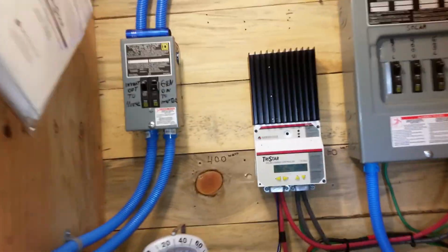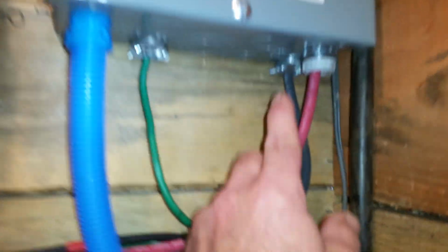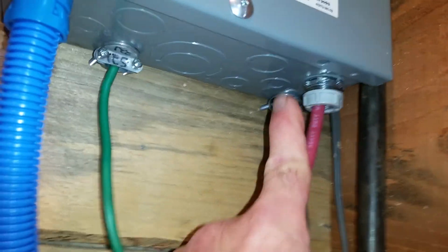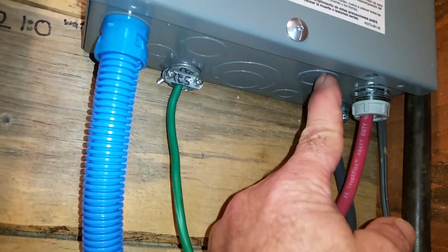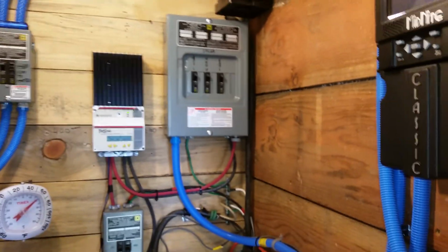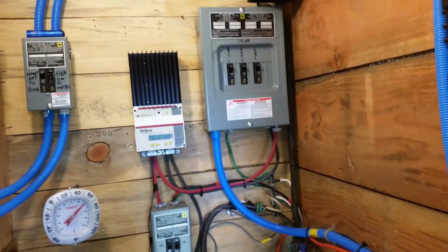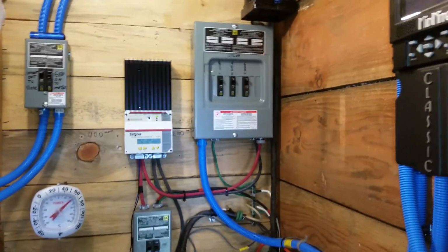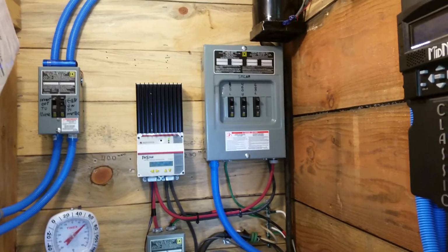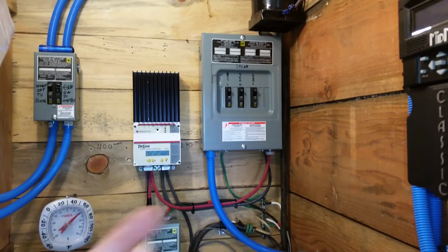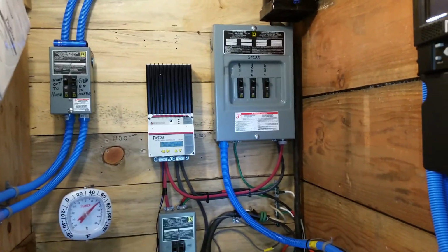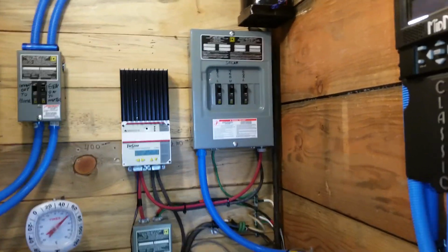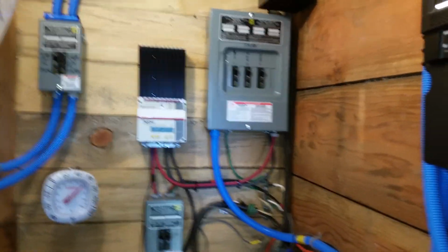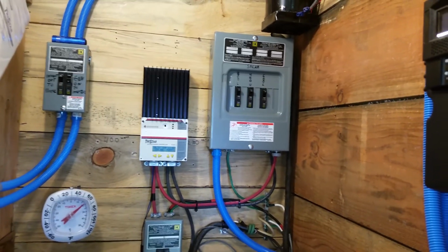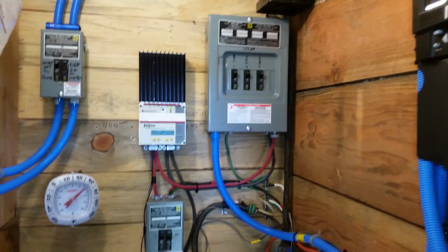Another thing I see is people put wire right into a knockout where there's a sharp edge, and that wire expands and contracts. When amperage goes through it, it warms up and expands, and when it cools off it contracts. That working back and forth on the sharp metal edge, eventually, if not now then 10 years from now, it will short out, and if it wasn't fused properly, you have a major fire on your hands.